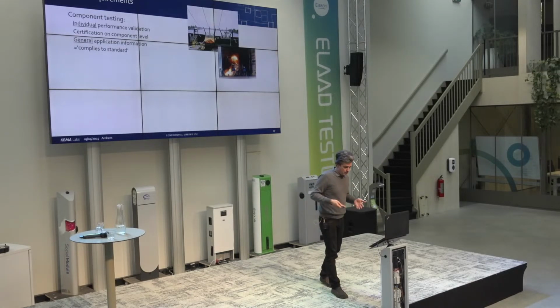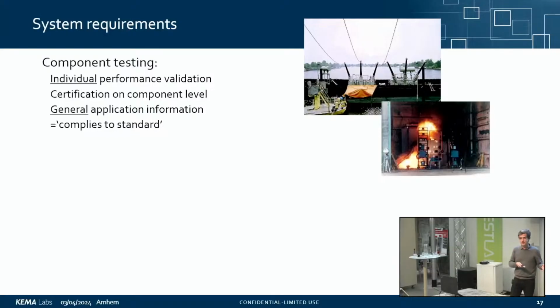So that brings us from what we have done before, which has been focused on component testing, where we have standards that are there, clear, harmonized or not, but are being used, where we can do testing in facilities like this, with or without certification behind it, to show that it complies to a standard. And that's great, and we should keep doing that, because that gives the quality of the product that you have in the market. But with these bigger systems, the risk is that that's not enough.